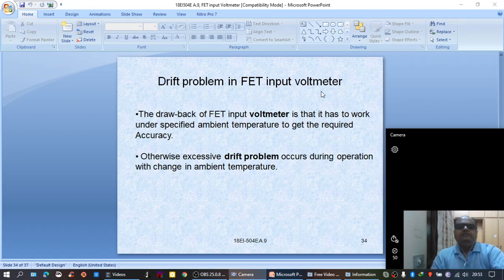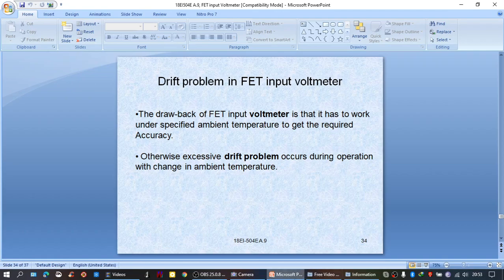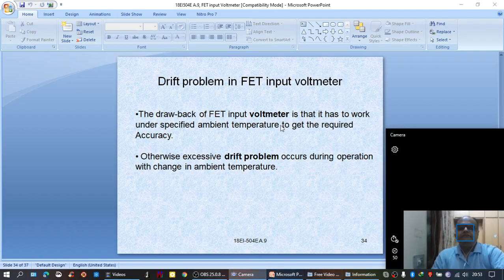Drift problem in the FET voltmeter. This is one point to be kept in mind while using the circuit. Drift problem, that is the effect of temperature. The drawback of the FET input voltmeter is that it has to work under specified ambient temperature conditions only. The manufacturer will give a range of temperatures under which it will provide accurate measurements.